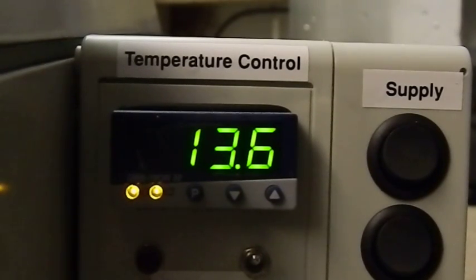Okay, the current set point on this controller is 13.6, and the machine is up to temperature and controlling at that temperature. So the temperature inside the machine, if I look at the thermometer, is actually 13.3. Now, this calibration can be done at absolutely any temperature. I tend to do it at a low temperature first as we test the machines to get it close, and then we do it again at 37.5 or whatever your incubation temperature is going to be as a fine calibration. So at the moment there is 0.3 variation between the controller and the known mercury thermometer. The mercury thermometer reading 0.3 degrees lower. Okay, we need to lower therefore the display by 0.3 of a degree.